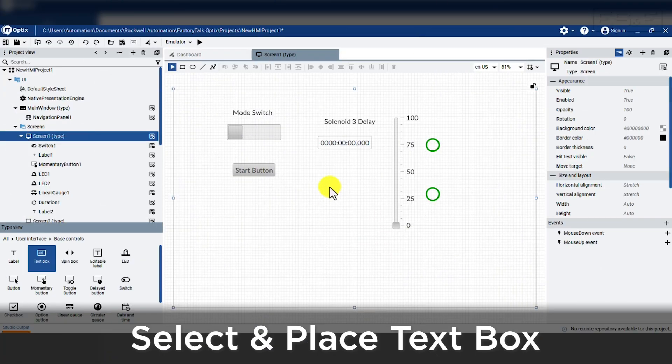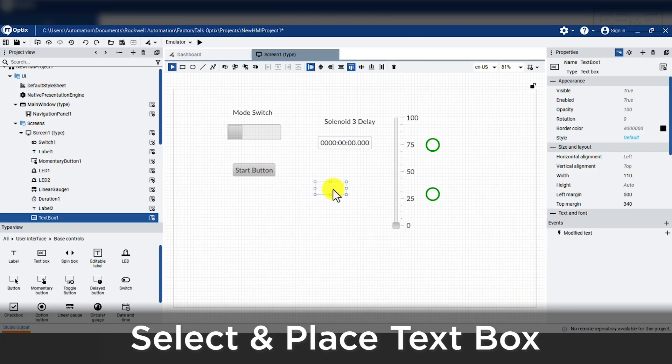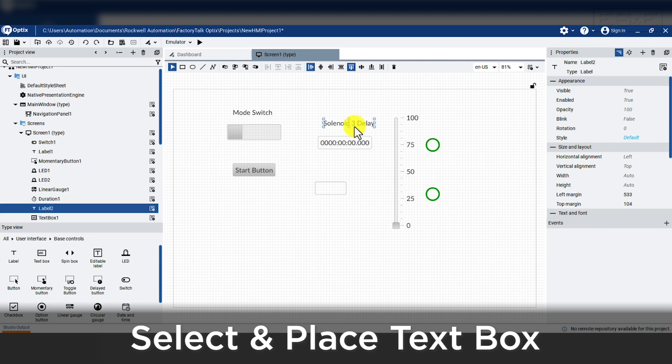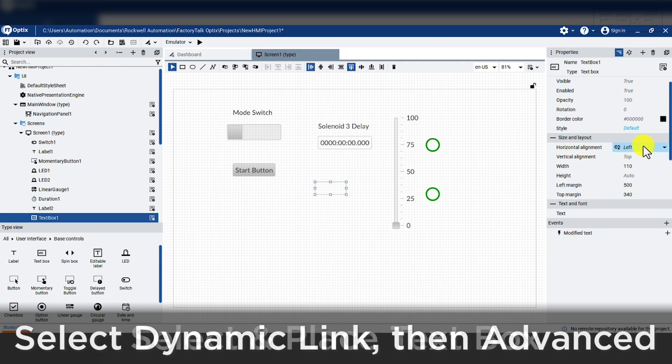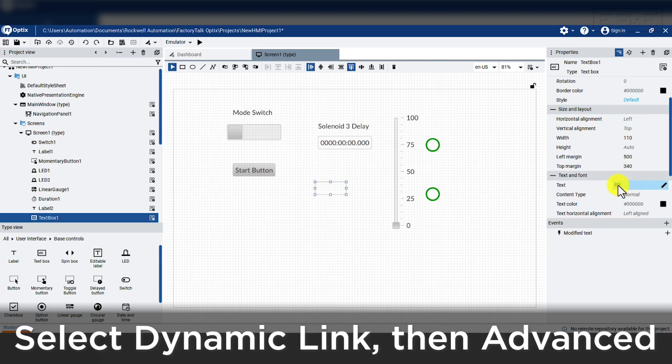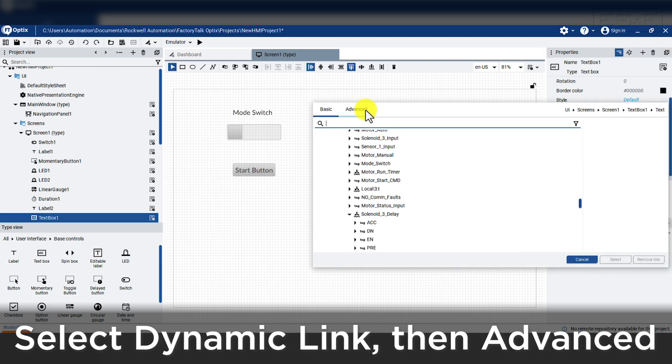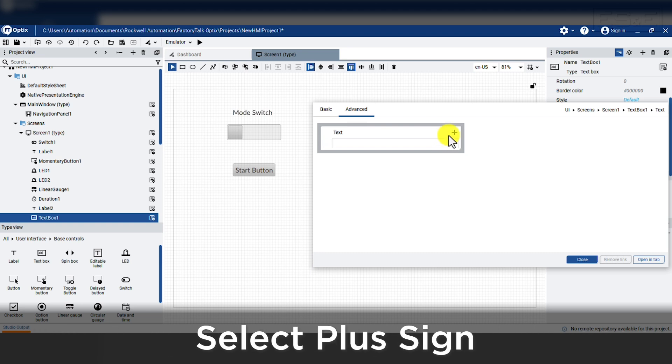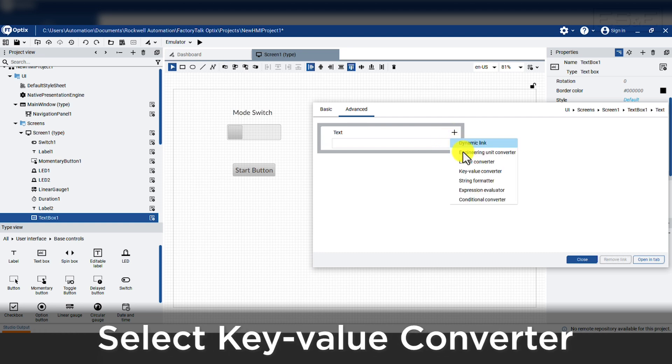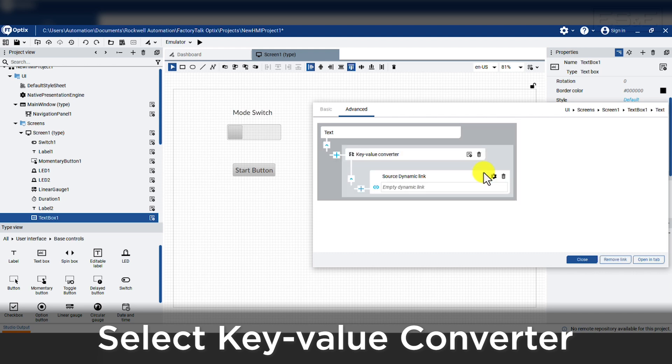Next, we will create a multi-state indicator from a text box. After we drop the box, we need to add a link next to the text. When the search menu appears, we need to select advanced. Then in the box where it shows the text, we need to hit the plus sign. This allows us to add new properties to the text object, but we want to select key value converter. The key value converter allows us to link a tag and convert a property based on that tag.